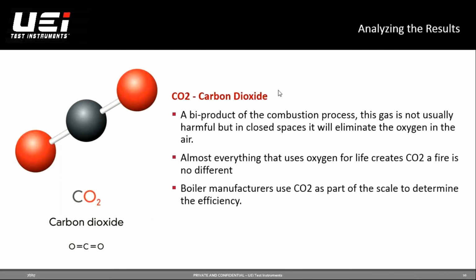The other thing about CO2, especially if you're doing a lot of boiler installs, is that a lot of the boiler manufacturers are actually not paying attention to what the CO and oxygen levels are, but they're actually wanting to know what the CO2 levels are. I got to do some training classes with various boiler companies, and one of the interesting things we talked about is that if the gas pressure was right and the CO2 levels were right, then everything was set up, because that's how they're determining their efficiency.